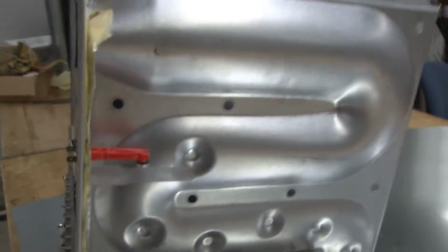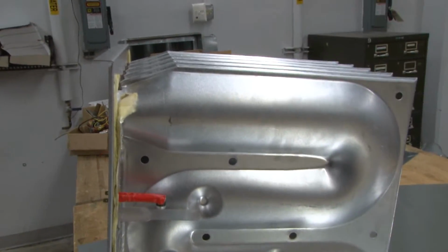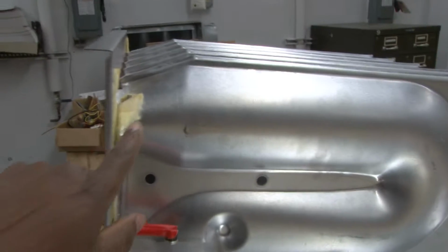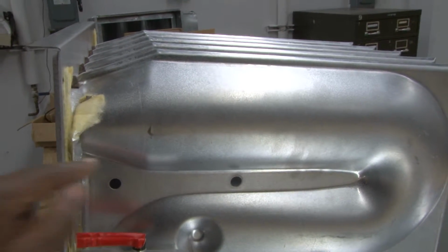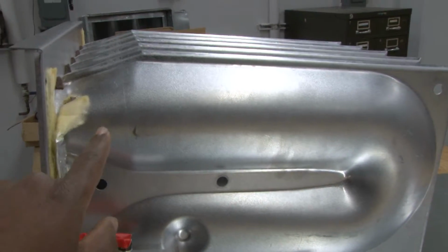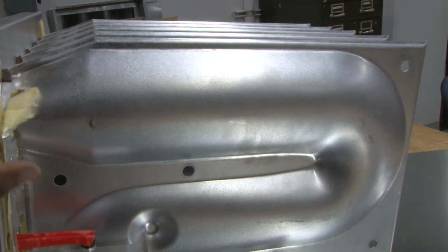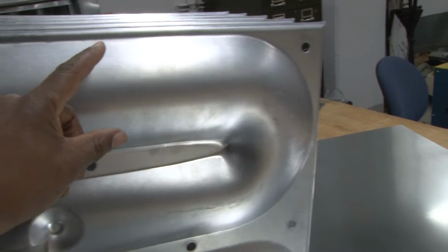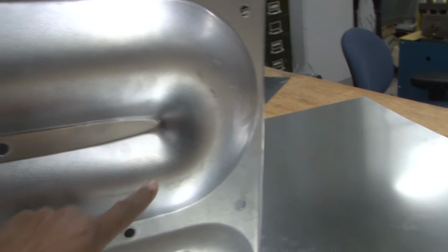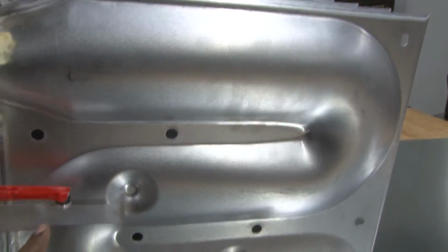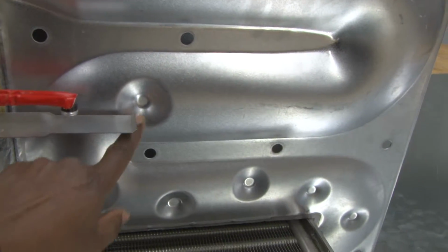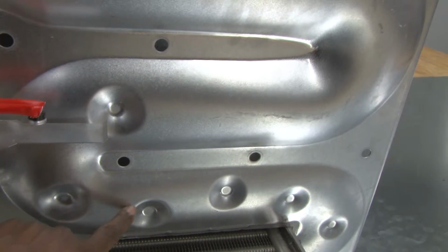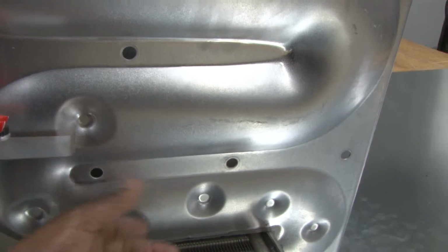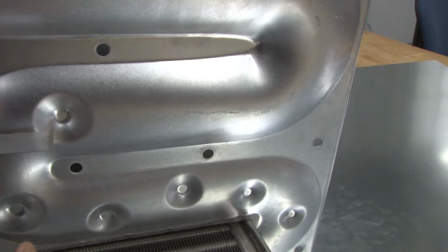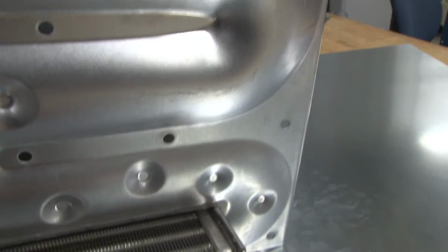As I back out, we can see the passages of the heat exchanger. Starting at the top, where the burner will be located on the outside, it's very large as the heat comes in, and as it goes through, these channels actually decrease in size as the velocity increases. Then they put these dimples in to actually slow down the flow so it can extract the heat out before it goes into the secondary heat exchanger.